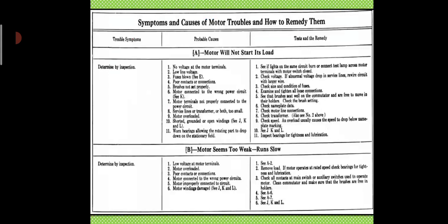Now, symptoms and causes of motor troubles and how to remedy them. Trouble symptoms are determined by inspection. Okay, when the motor will not start its load, the causes are: no voltage at the motor terminals, low line voltage, fuse blown, poor contacts or connections, brushes not set properly, motor connected to the wrong power circuit, motor terminals not properly connected to the power circuit, service lines or transformer or both too small, motor overloaded, shorted, grounded or open windings, worn bearings allowing the rotating part to drop down on the stationary part.